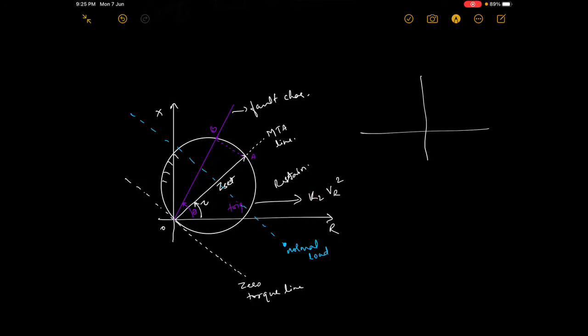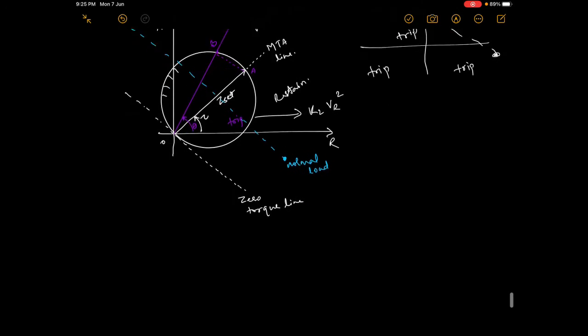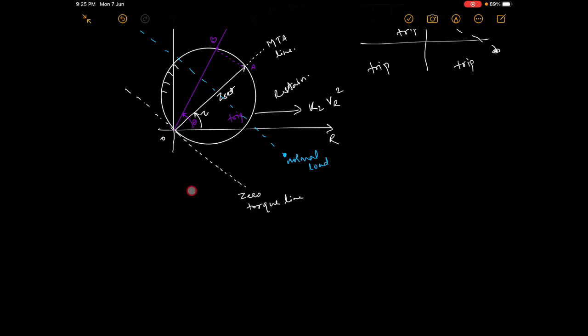Whereas in the reactance relay, you had a reactance line like this. So here for normal load, anything below this reactance line was considered a fault, that is, it was tripping, right? Yes. So it was operating on a fault assumption, which was a malfunction, but here that malfunction doesn't happen. So this is one of the advantages. And we have other advantages also, we will see them.